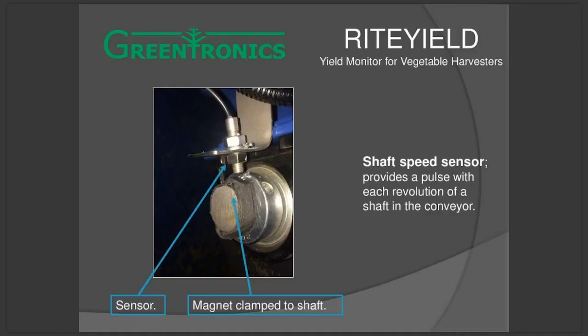It's up to the end user, really, whatever is more convenient. If you have a slow running shaft, so say less than 30 RPM, you might want to put 2 magnets on the shaft. So we put 2 in every kit. So you put them opposite each other. That way we get 2 pulses per shaft revolution. It helps things a little bit.